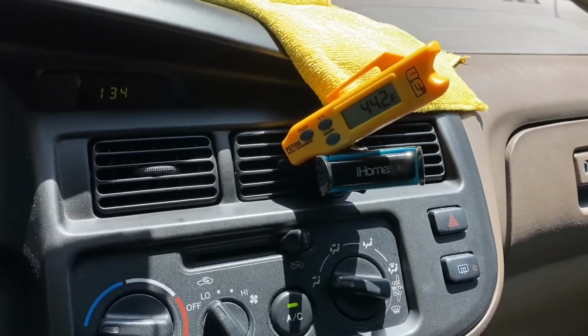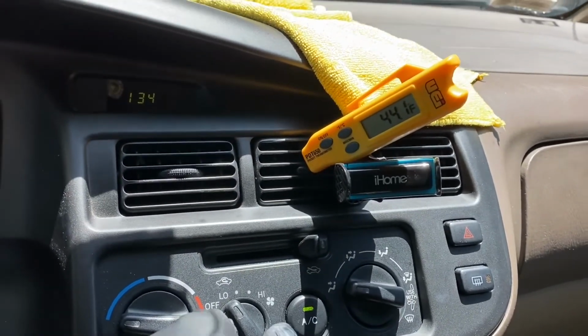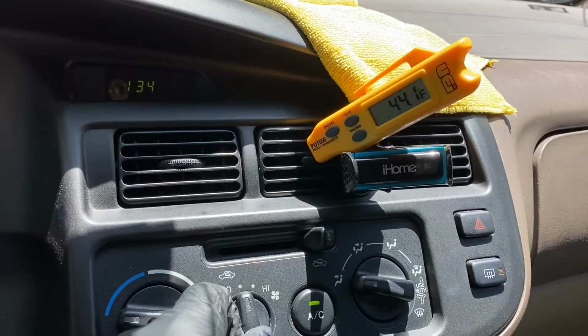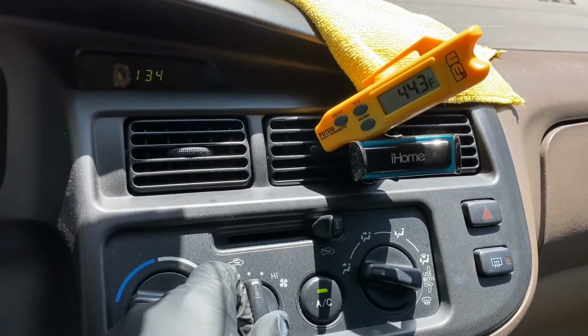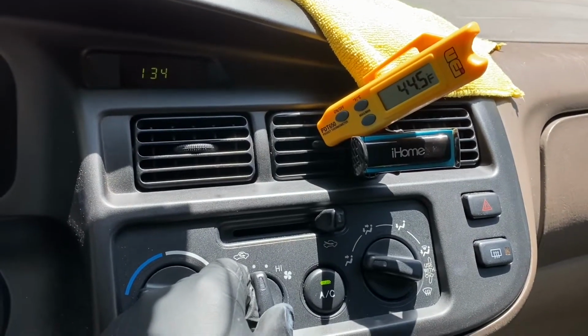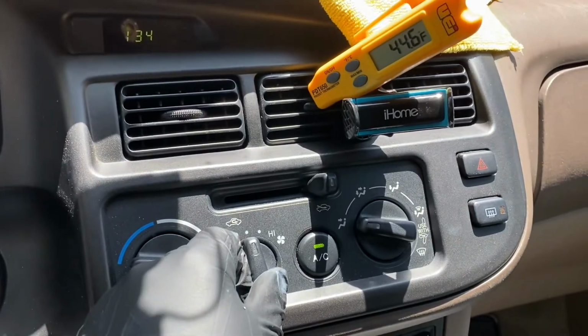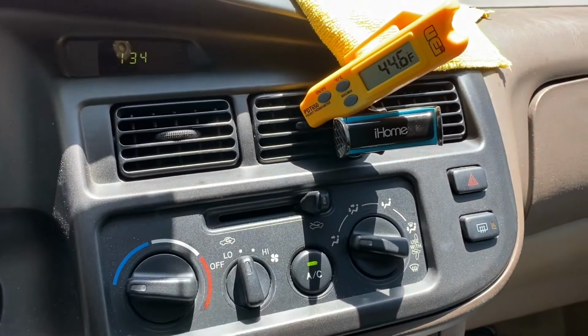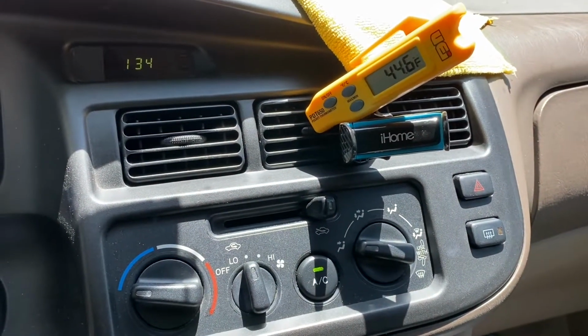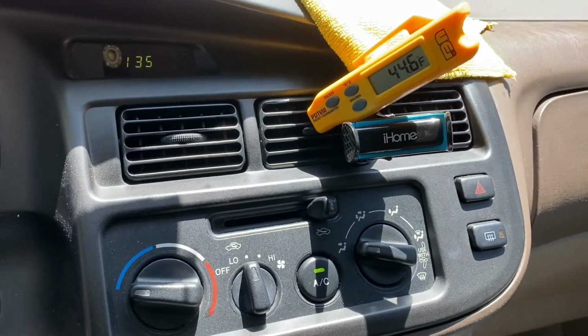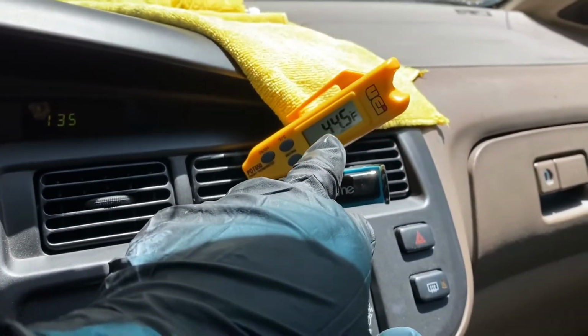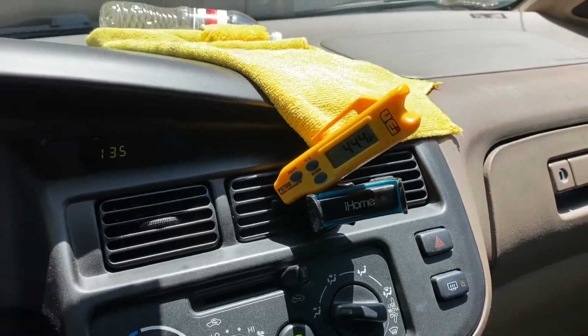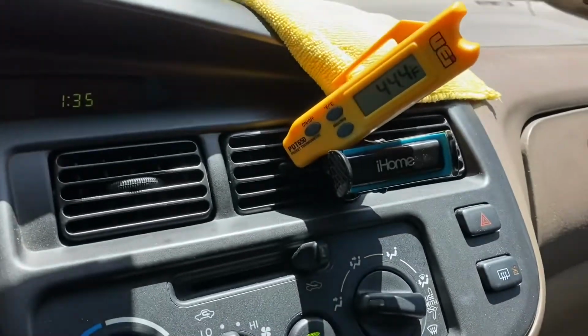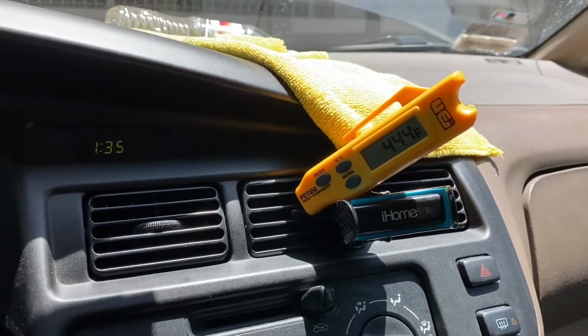But as soon as I increase the heat load, increasing the amount of air going through the evaporator and the amount of heat that airflow brings, I might see the temperature start to rise, and the pressure on the low side, the vapor side, should also rise.